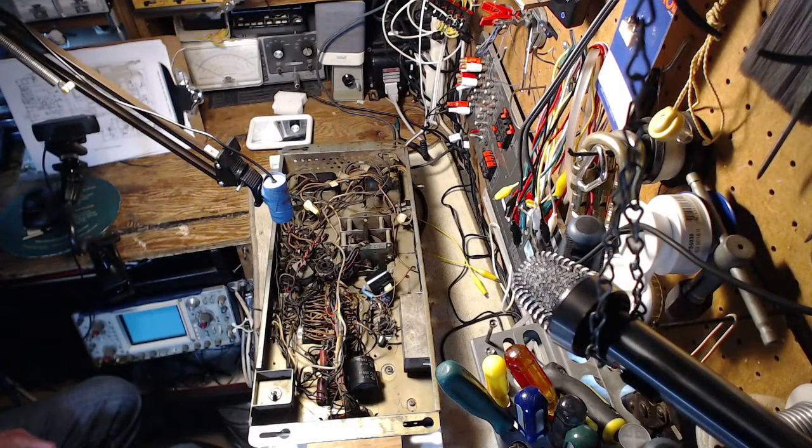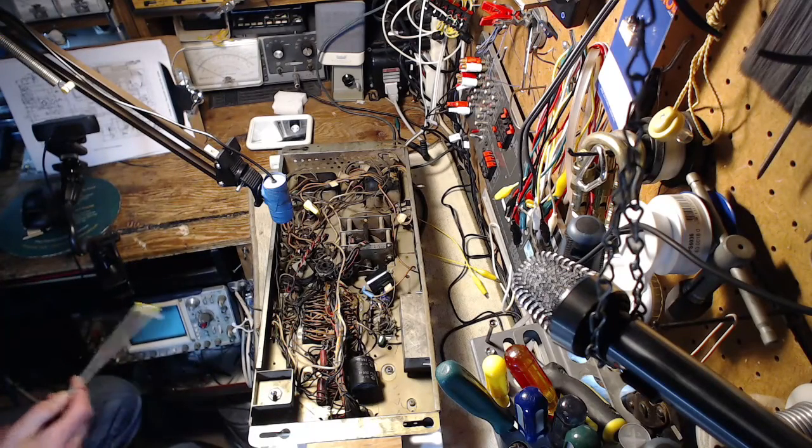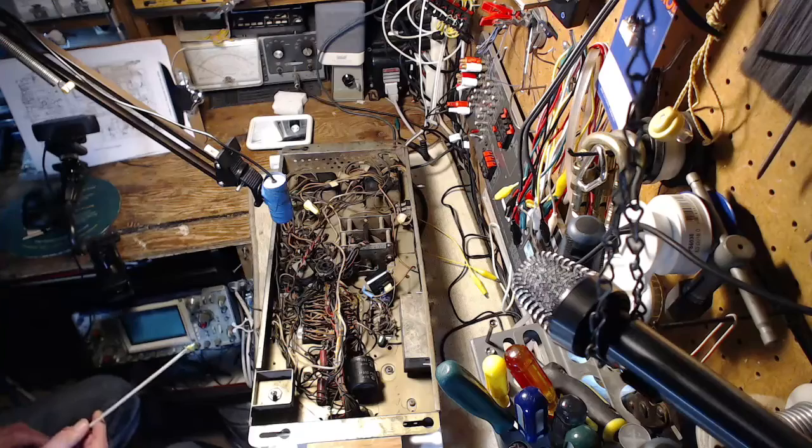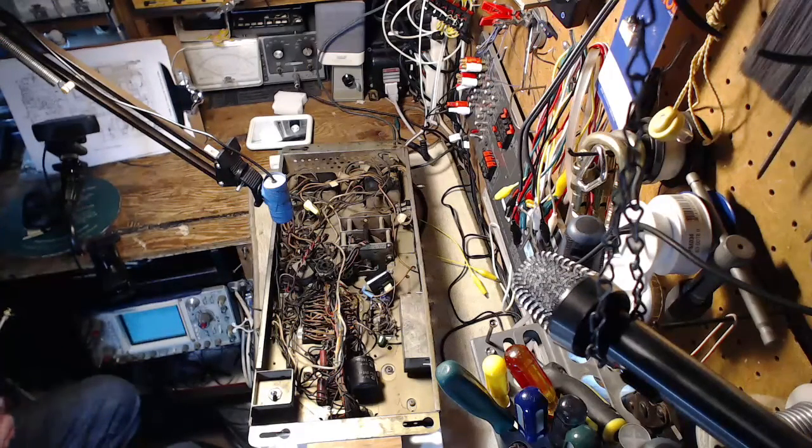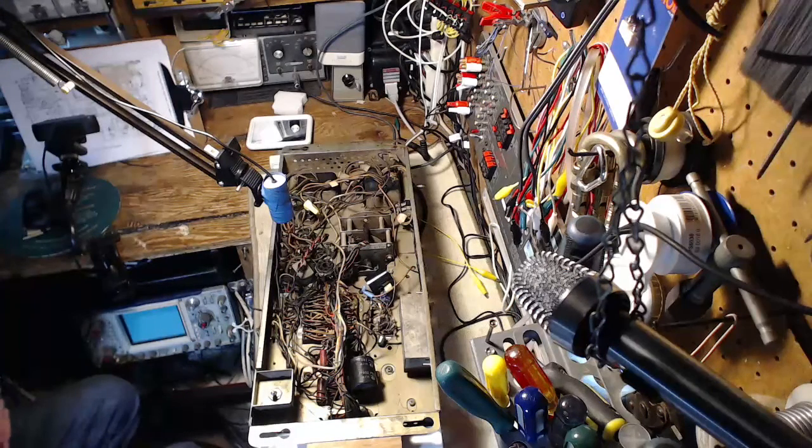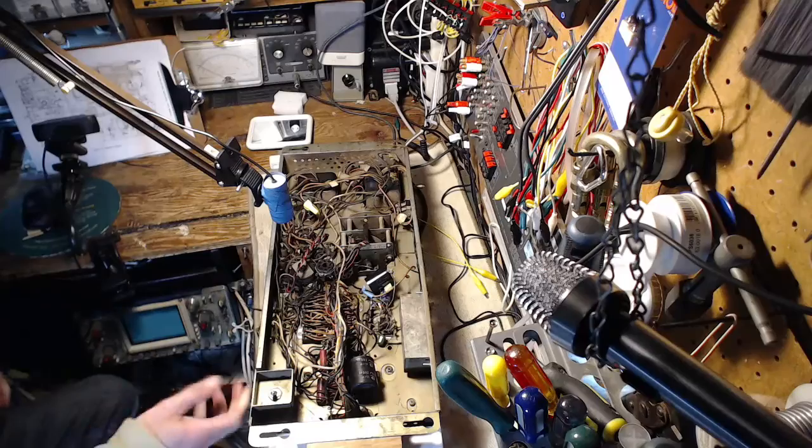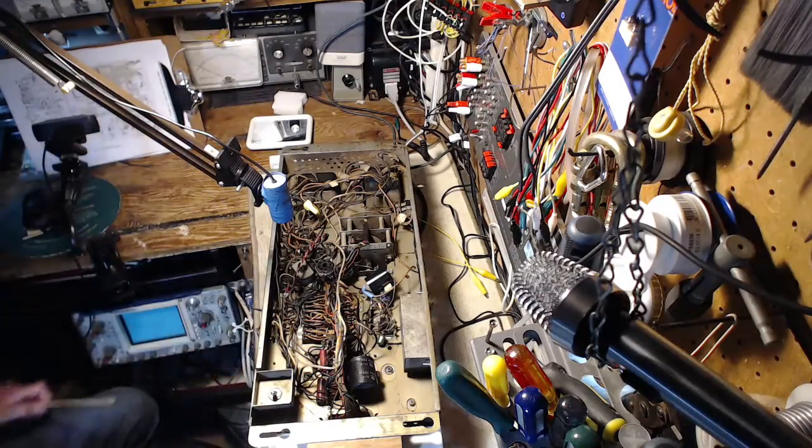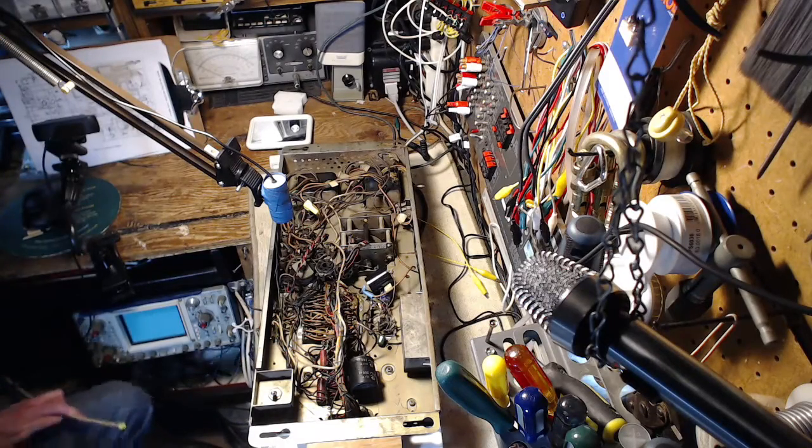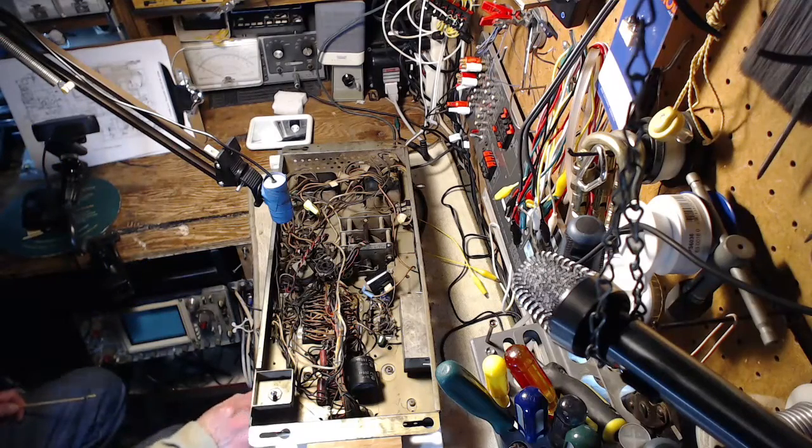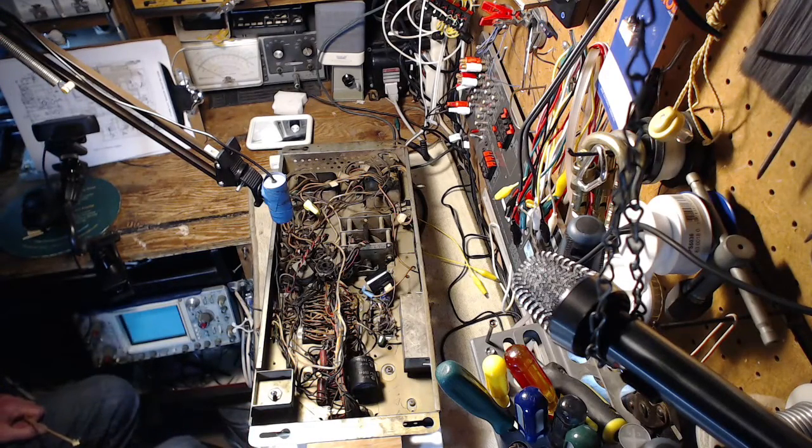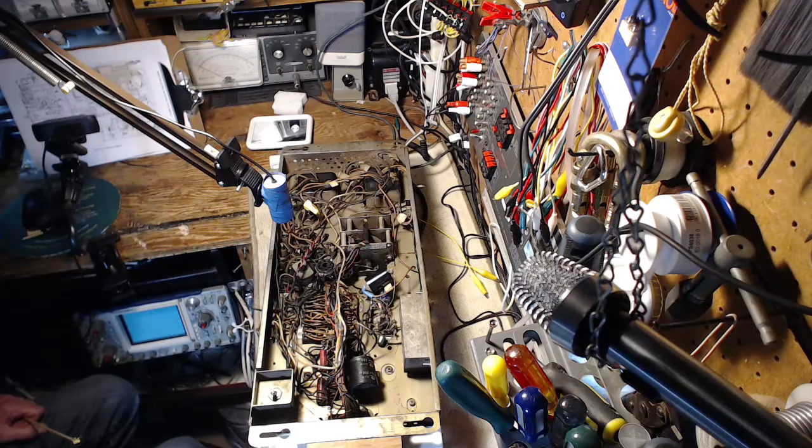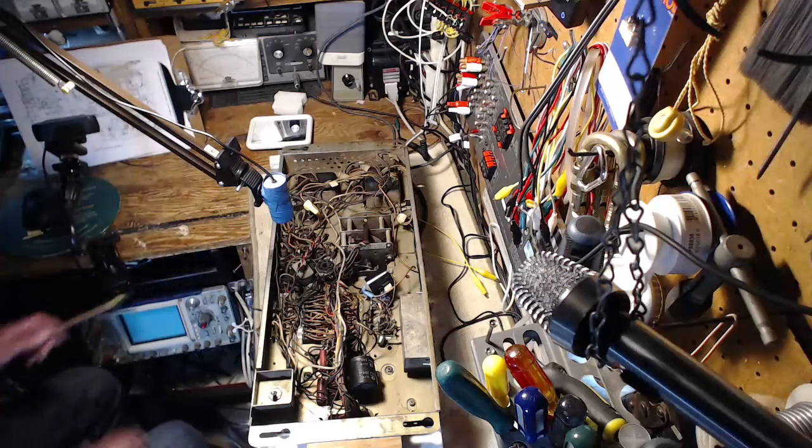And I think it's really important to get down to the bottom of this. So, probably some simple test by taking the plug end and just testing the resistance back up into the electrical selector. You know, what am I gonna see? I'm gonna see a short circuit. What else can I see? If I already know the results of the test, I don't have to make the test. I should be taking a look at the schematic for that electrical selector.